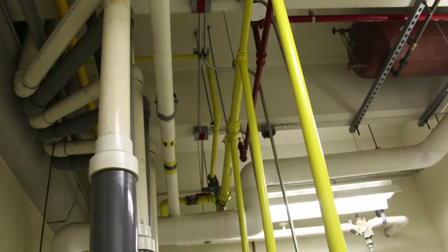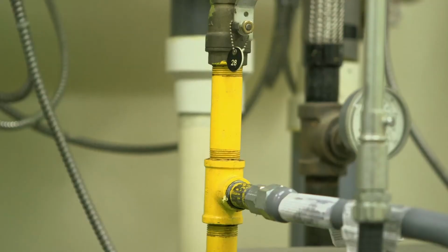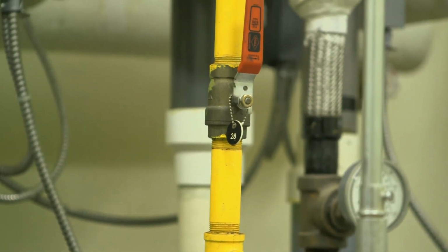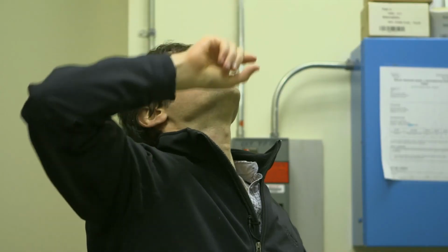Another thing that you may want to consider almost in all cases is to look at the piping configuration and understand how the heating plant is tied into the main hot water supply of the building. So in this case, we know that these boilers are only running in the summer, so they're probably going to be using the pump above here. Can you see the pump? So the pump, this is basically the boiler pump in this case, circulates the water through the boilers.